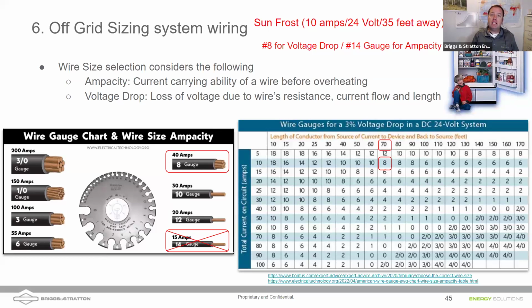But if you start to get too far away, what starts to happen is voltage drop. We don't see voltage drop really being a concern in 110 or 220 volt systems. But when we're doing lower voltage, like 24 or even 48 volt systems with DC loads, voltage drop starts to become a concern faster than ampacity does. So if we have a fridge that's 35 feet away, we need 8-gauge wire to allow that fridge to run with only about a 3% voltage drop.